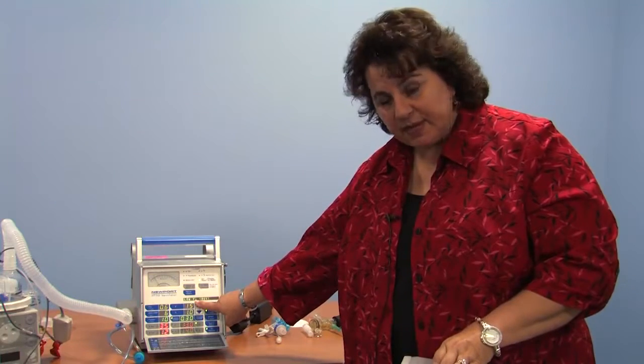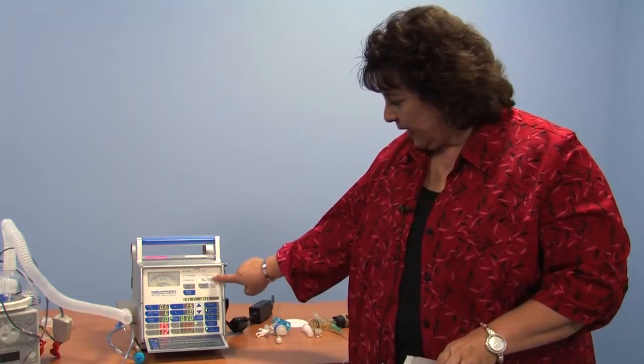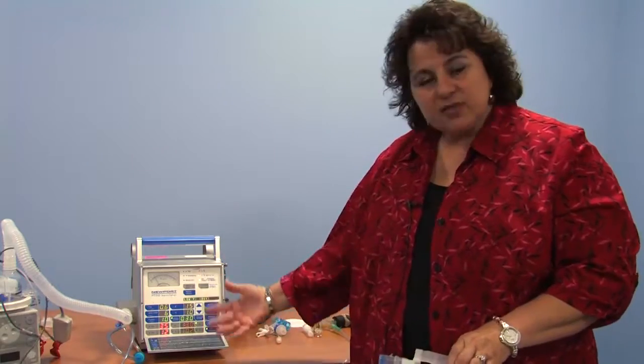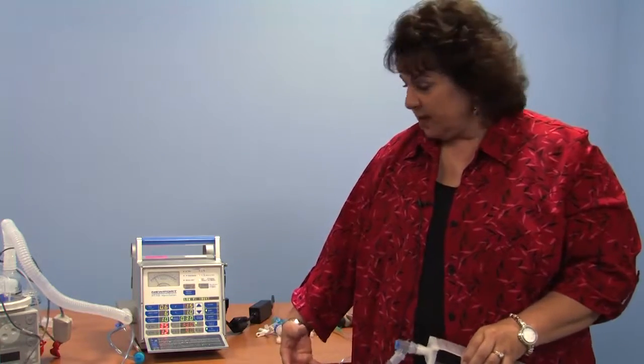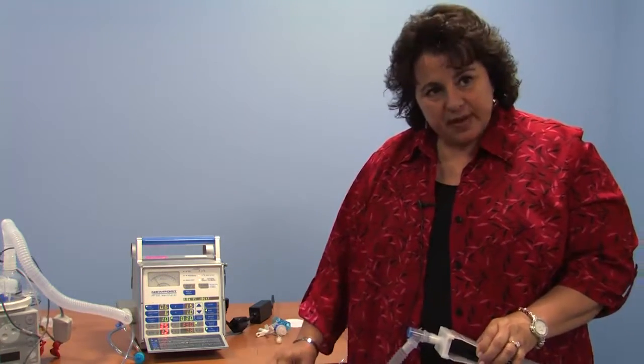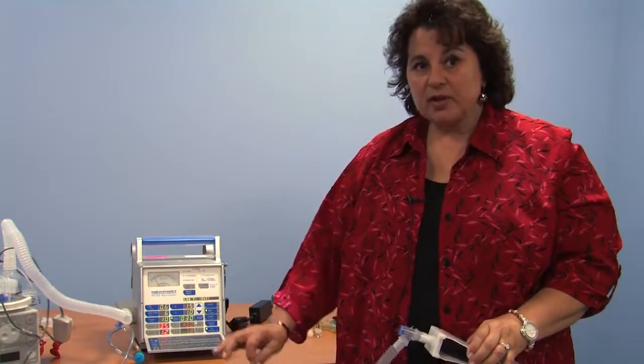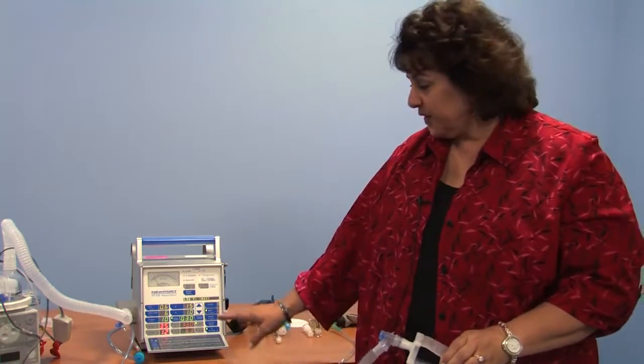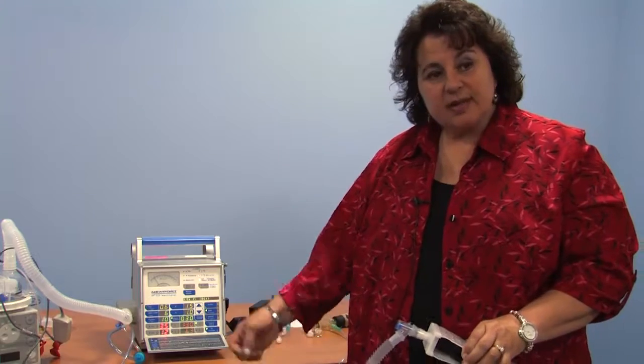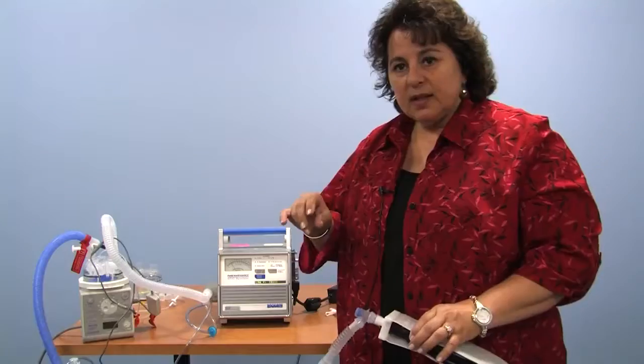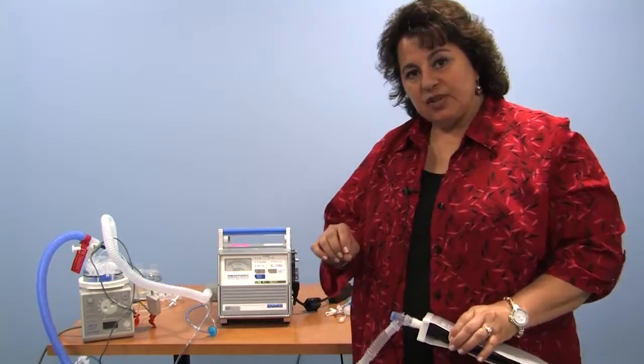Low VE, or minute ventilation, backup ventilation, flashing and alarming. What it does, it has automatic settings that it goes to. It doubles certain things when it senses that the patient isn't breathing enough air that you asked it to alarm for. So that is backup ventilation. It's preset, with nothing for us to adjust. It's based on the numbers and the settings that your child is on. But it does alarm to tell you that. So if it's saying BUV, backup ventilation, that's a low minute volume alarm, and the machine is now firing mandatory breaths. Let's review the alarms on the HT50 ventilator.